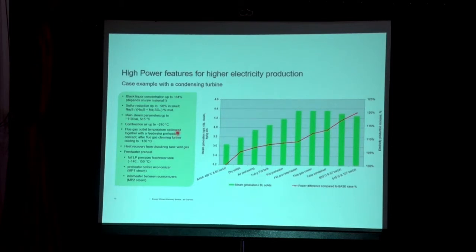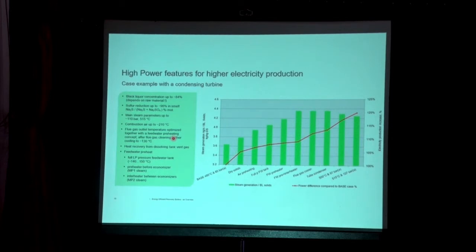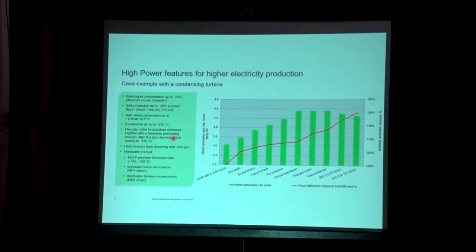Combustion air heating helps increase steam generation. Demi-water heating helps reduce LP steam consumption, which increases turbine efficiency. Heat recovery from the dissolving tank vent gas can be taken to the demi-water and the feed water preheat. We can have three feed water preheating stages: an LP full-pressure feed water preheater, an economizer, and an inter-heater placed between economizer stages. These are key parameters when compared to conventional boilers, which produce steam generation of around 3.6 to 3.7 kg per kg of dry solids.